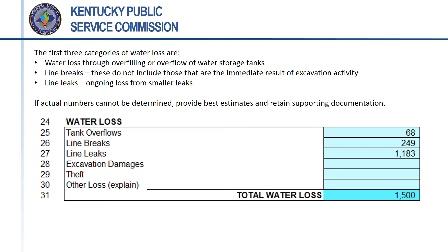Line breaks should include water lost by a severing or other major failure in a water line that leads to a loss of service or pressure to all or part of the system. Line breaks that are the immediate result of excavation damage should not be included in this category. Line leaks include all water lost through chronic leaks in distribution lines other than those severe enough to be categorized as line breaks. Generally, a line leak will not require immediate repair, whereas a line break will create a loss of service or pressure and need to be repaired immediately. Because these numbers are often hard to determine with precision, it is acceptable to use best estimates — make sure to retain supporting documentation.